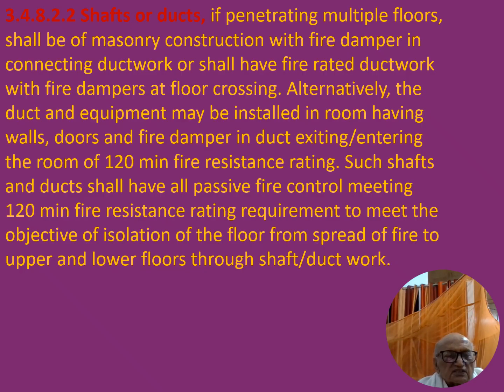Friends, this is about passing of shaft or duct if penetrating multiple floors shall be of masonry construction with the fire damper in connecting ductwork or shall have fire rated ductwork with fire dampers at floor crossing. Alternatively, the duct and equipment may be installed in room having walls, doors and fire damper in duct exiting or entering the room of 120 minutes fire resistance rating. Such shaft and duct shall have all passive fire control meeting 120 minutes fire resistance rating requirement to meet the objective of isolation of floor from spread of fire to upper and lower floors through the duct work.